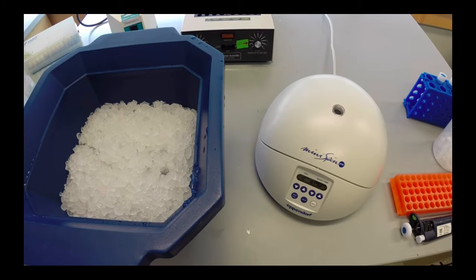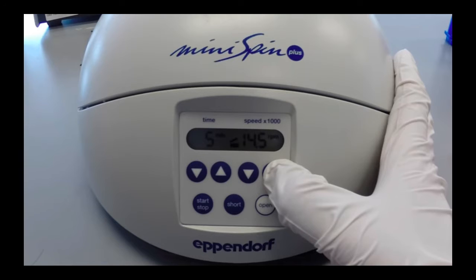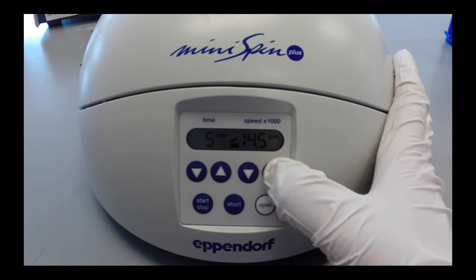Change the centrifugation time by pressing the arrows to the desired time, in this case, 5 minutes. Press the arrows by the speed to navigate to the proper RPM. In this case, 14,500 RPM is the max this centrifuge can perform and is close enough to our desired speed. Press the start button. The centrifuge will begin to spin.